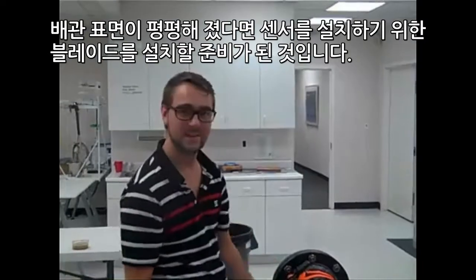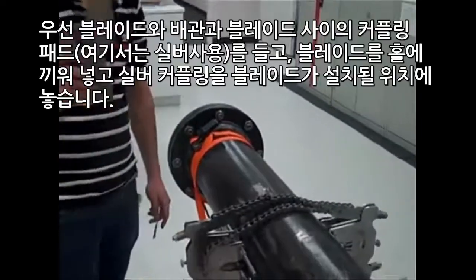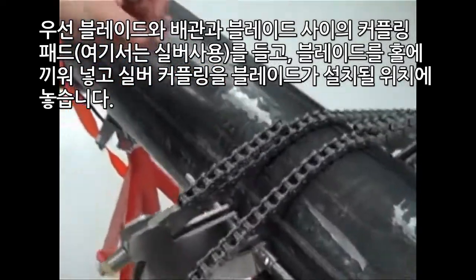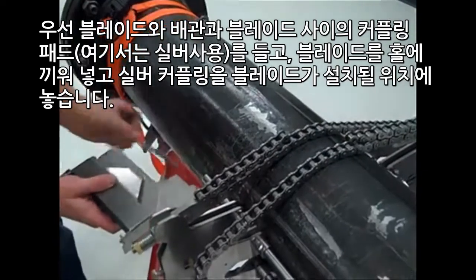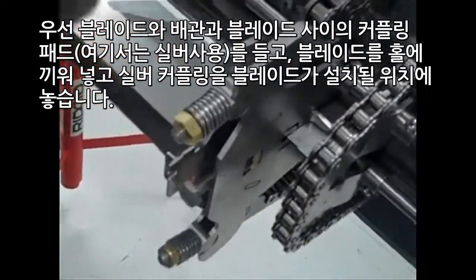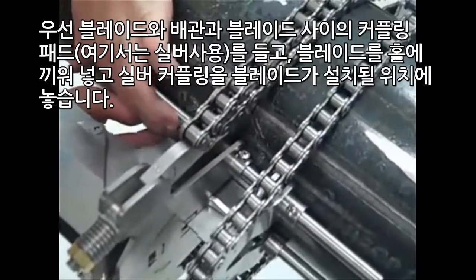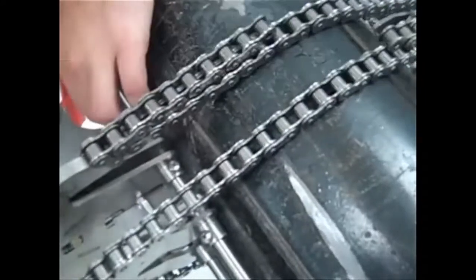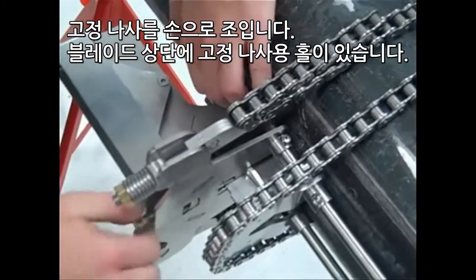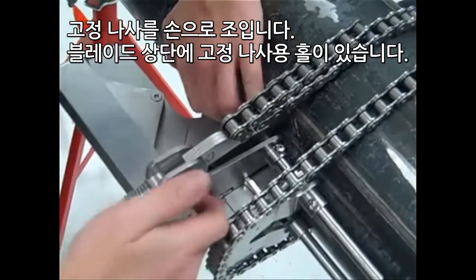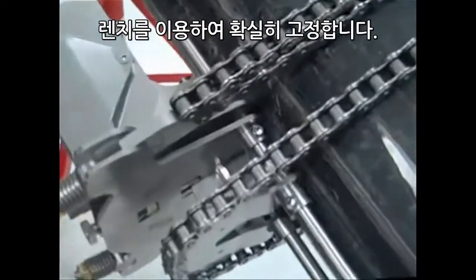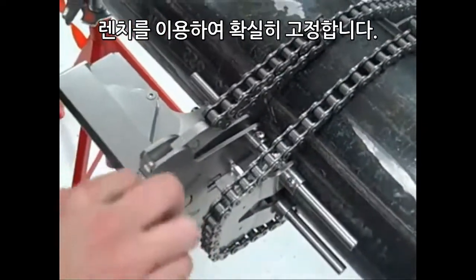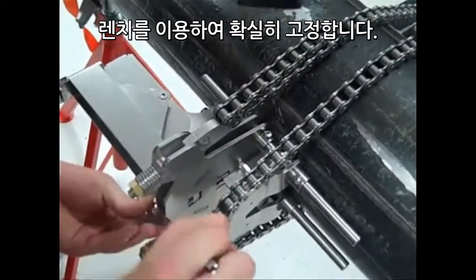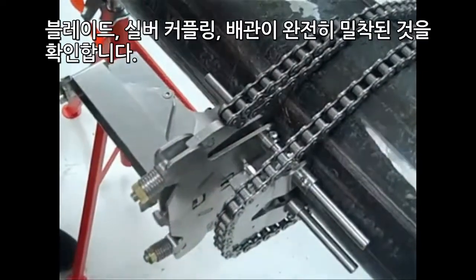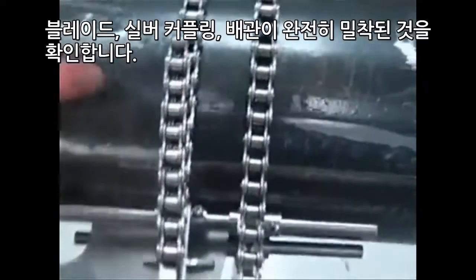After your surfaces are prepped, it is now time to install your blades for your transducers. So first step is to take the blade and silver. We're going to be using silver as a surface, as a coupling pad. You want to push your blade into the slot and place the silver underneath where the blade is going to be mounted. First step is to hand tighten the set screw. Remember the set screw, there is a slot for the set screw on top of the blade. And using your wrench, you want to tighten down firmly on silver, making sure that there is full contact between the blade, the pipe, and the silver. Next step is to repeat on the opposite side.